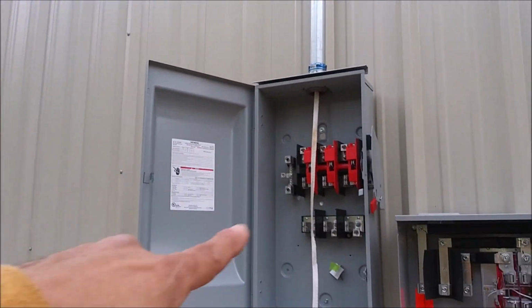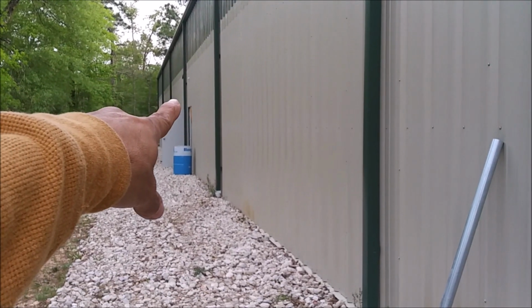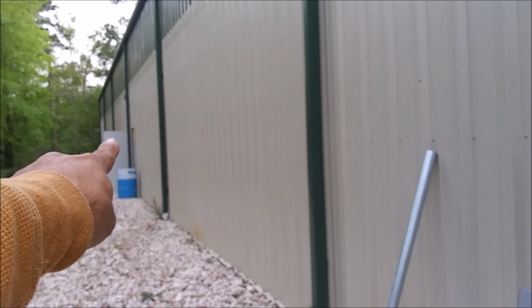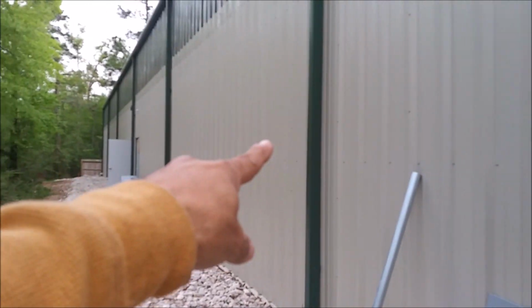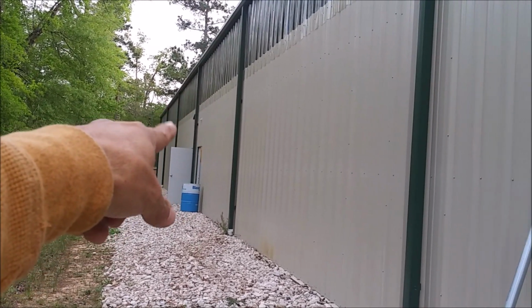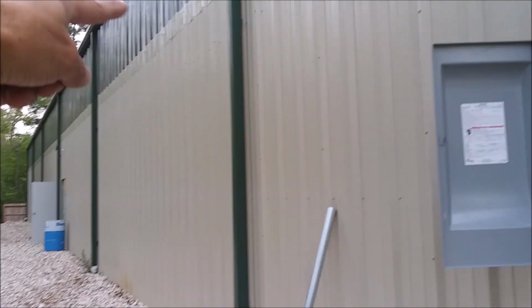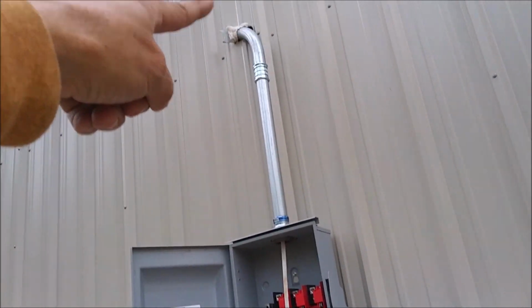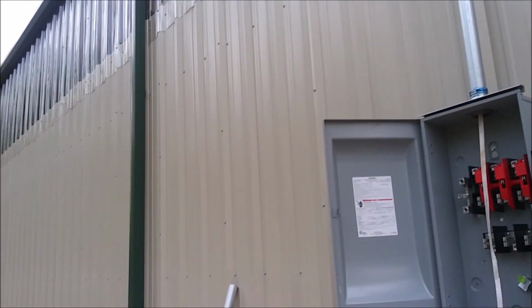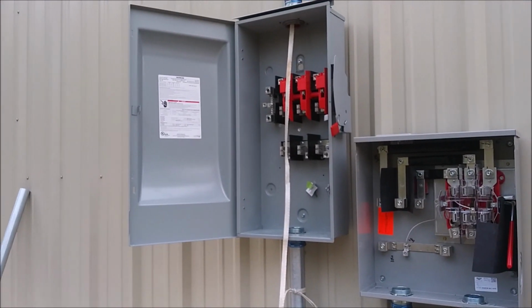This is 120, from green gutter to green gutter is 25 feet. So we got 100 feet, and then about this much drop, 5 feet. So 110 feet. We're going to pull this, and we'll start doing that shortly.